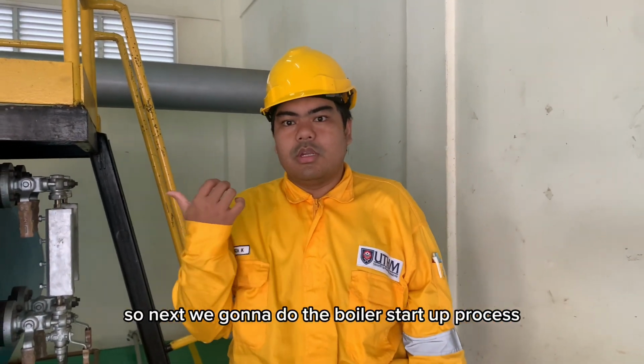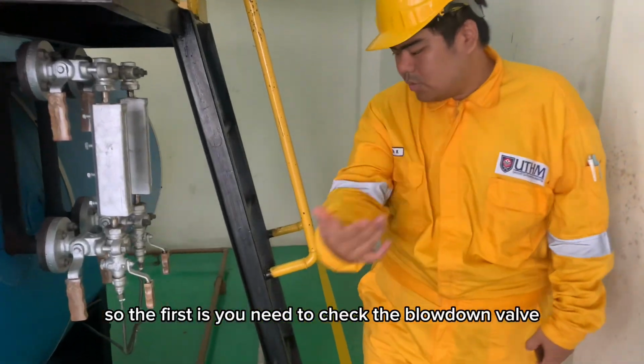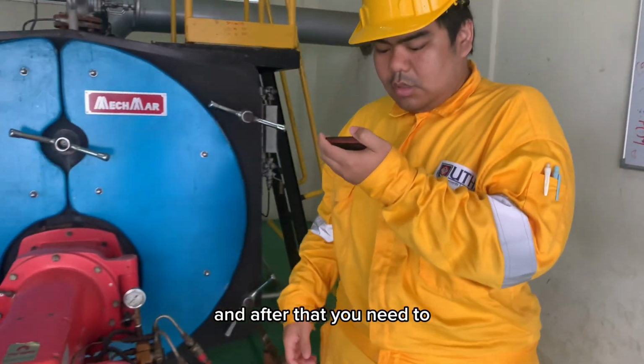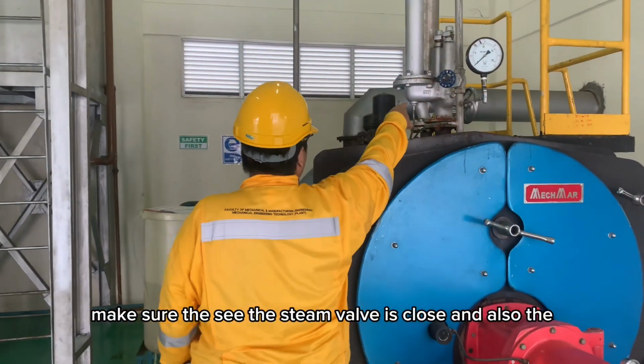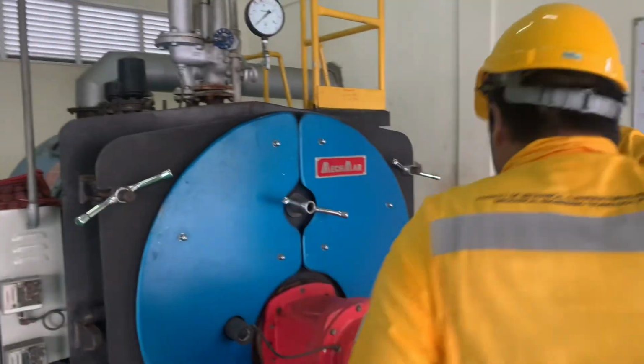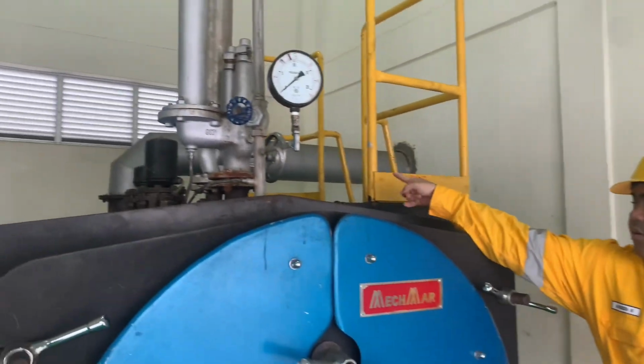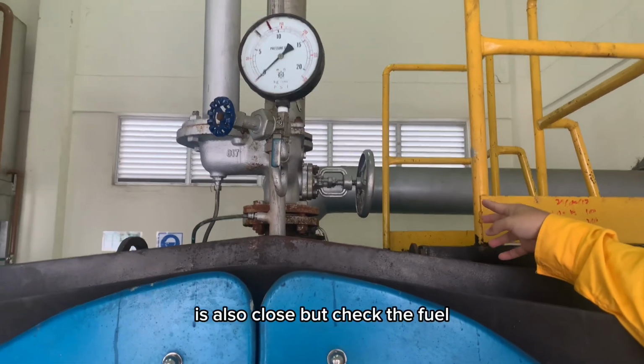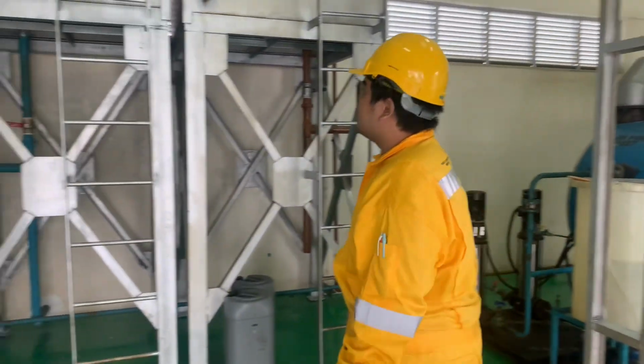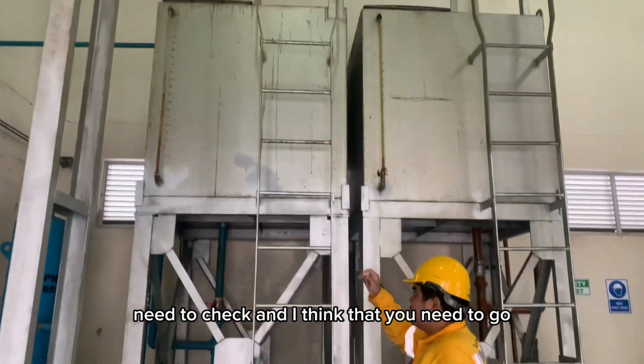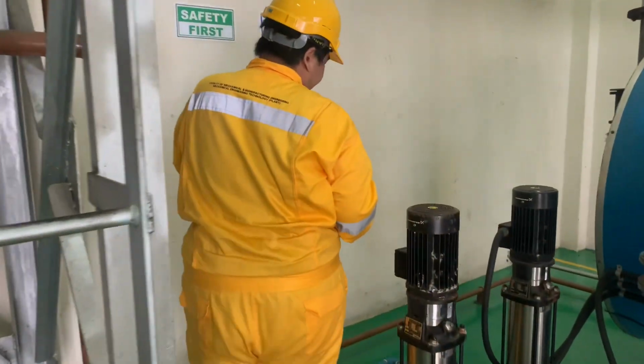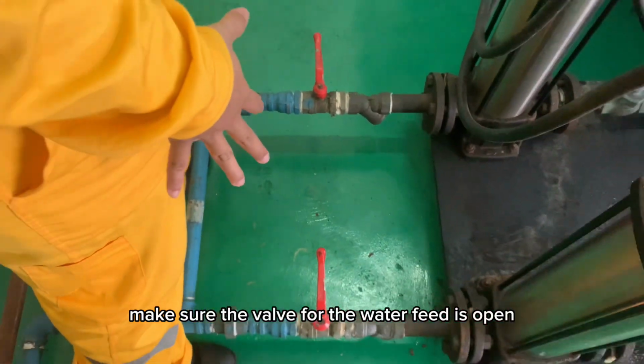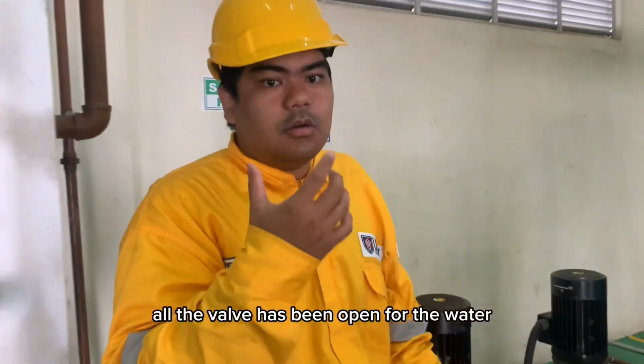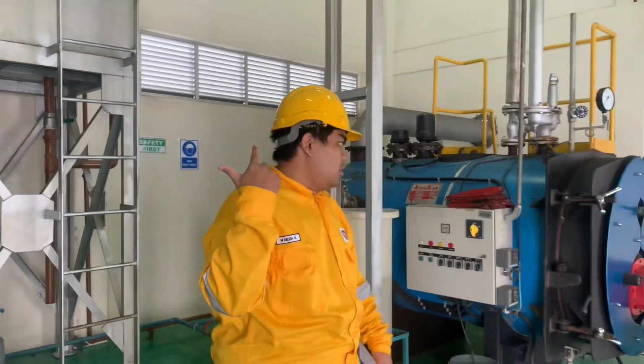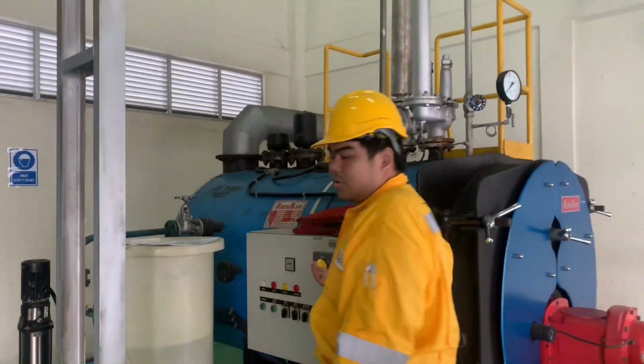So next, I'm going to do the boiler startup process. The first is you need to check the drain valve, make sure that it's closed. After that, you need to make sure the steam valve is closed, and also the main steam valve. Check the fuel. After that you need to make sure the valve for the water feed is open. After you check that all the valves for the water feed and the oil are open, then you can start running the boiler.